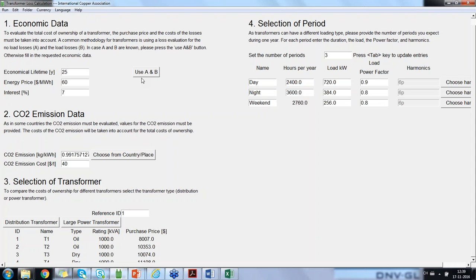Okay, just to add, essentially, the voltage harmonics probably will impact the hysteresis and eddy current loss, which in any case is a minuscule percentage of the total loss. So the impact of voltage harmonics probably will not be so heavy when we are considering our day-to-day use of this tool, and the current harmonic consideration currently taken should serve our purpose as a basic user rather than becoming a complicated designer experience. It is from the application point of view.